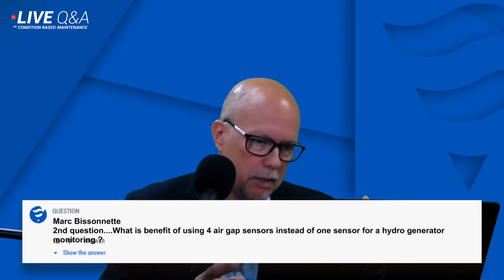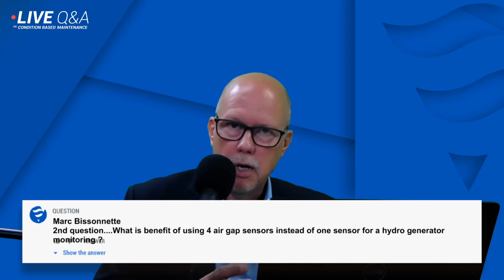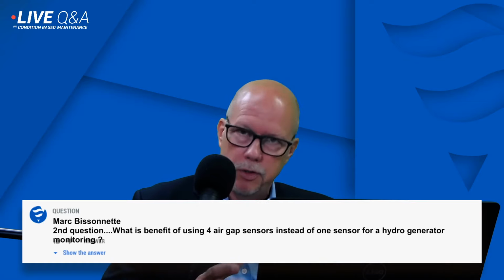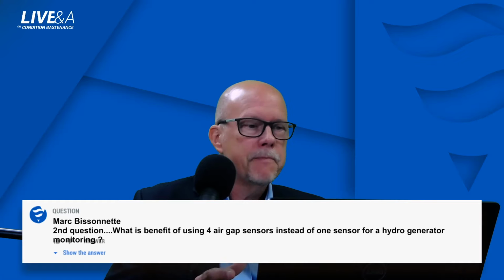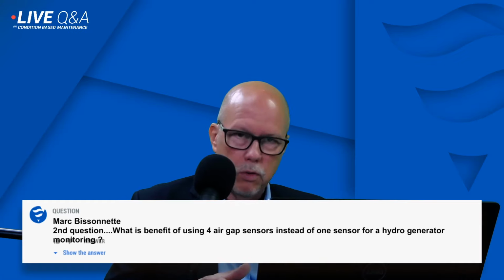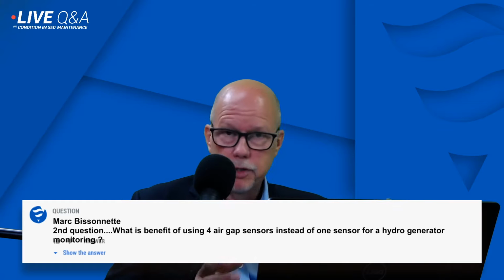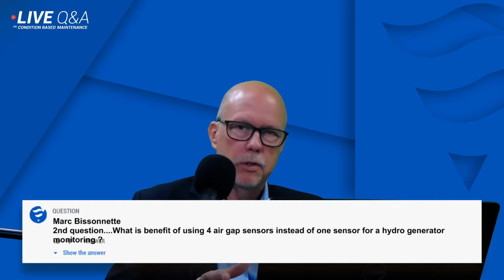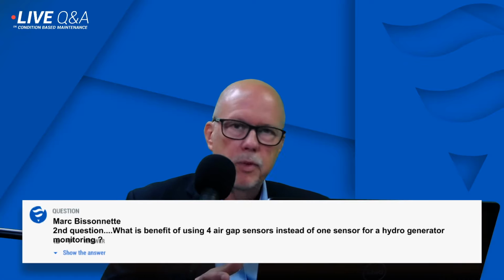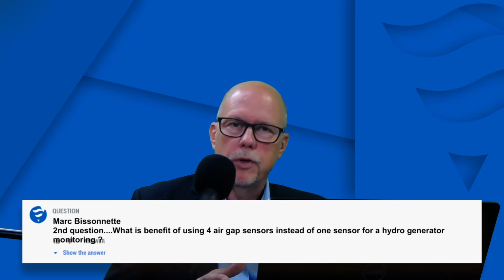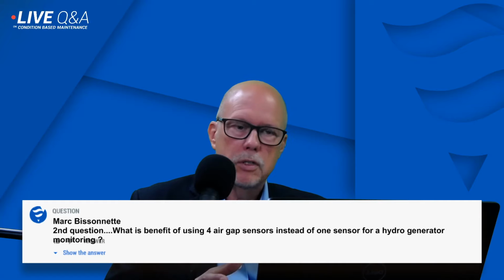And remember that when the units are full load, hot, that's where you usually want the unit to be, because that's where you're making money. There's a lot of people who take measurements cold, physical measurement, which is fine. It gives you an idea what the shape is when the unit is stopped and cold. But that's not really what you want to know. You want to know what the unit looks like when it's operating.